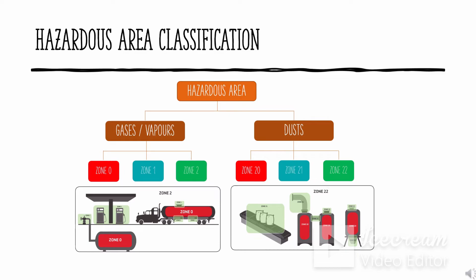Hazardous areas are classified in terms of zones and divisions. Zones are classified under IEC standards, whereas divisions are classified under North American NEC standards, on the basis of the frequency and the duration of the occurrence of an explosive atmosphere. Under zone 0 and zone 20, explosive atmosphere is continuously present. Under zone 1 and zone 21, explosive atmosphere is likely to occur in normal operation. Under zone 2 and zone 22, explosive atmosphere is unlikely to occur, but if it does, it will exist only for a very short period of time.